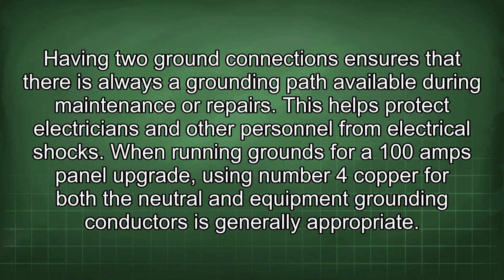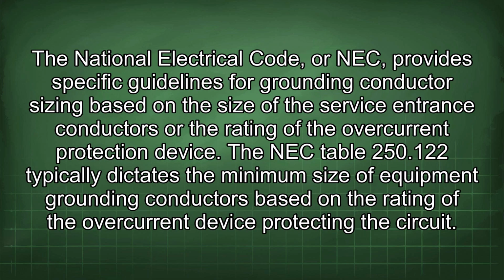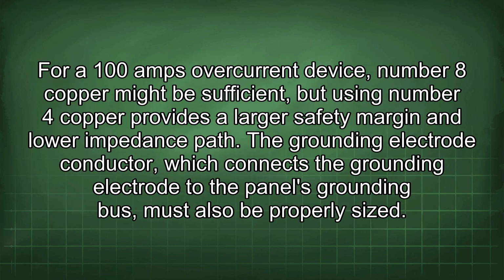When running grounds for a 100 amp panel upgrade, using number 4 copper for both the neutral and equipment grounding conductors is generally appropriate. The National Electrical Code, or NEC, provides specific guidelines for grounding conductor sizing based on the size of the service entrance conductors or the rating of the overcurrent protection device. NEC Table 250.122 typically dictates the minimum size of equipment grounding conductors based on the rating of the overcurrent device protecting the circuit. For a 100 amp overcurrent device, number 8 copper might be sufficient, but using number 4 copper provides a larger safety margin and lower impedance path.